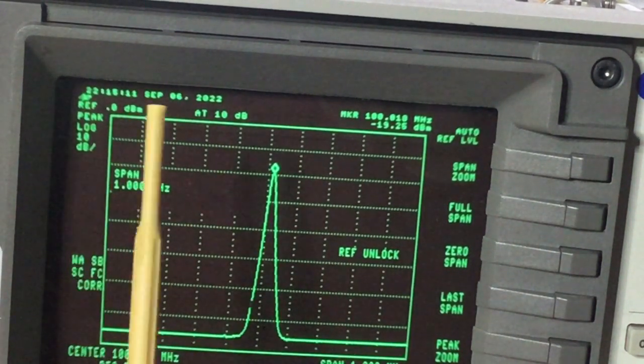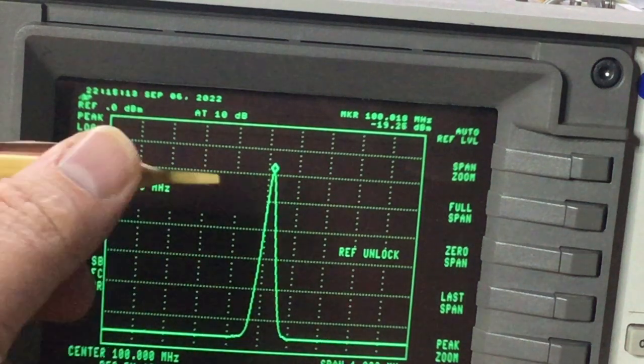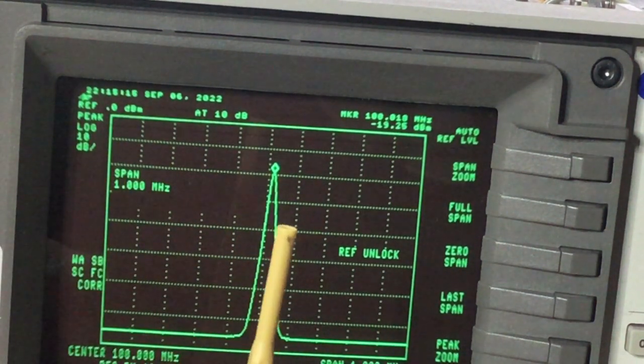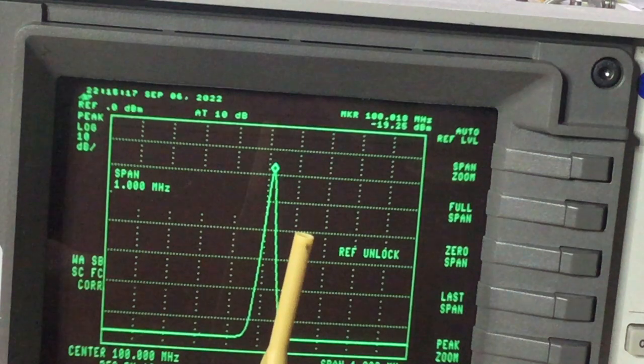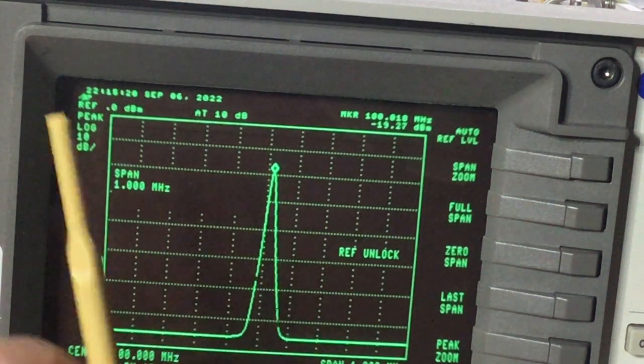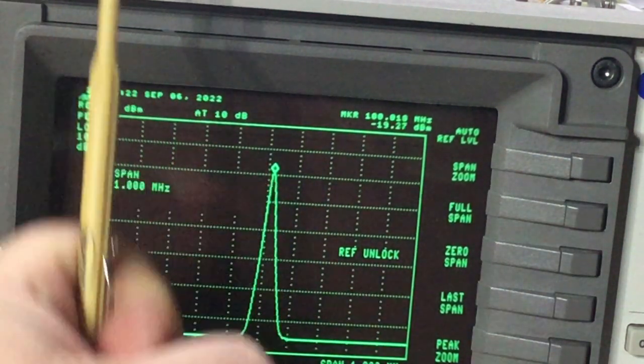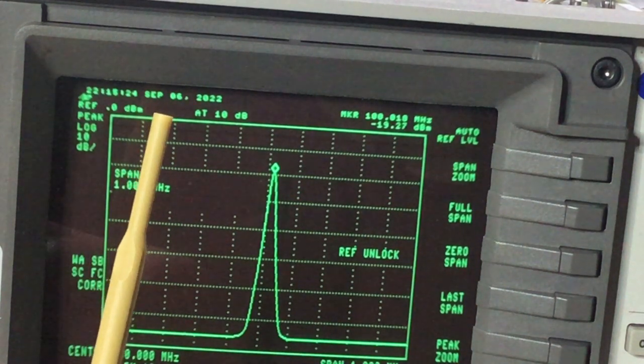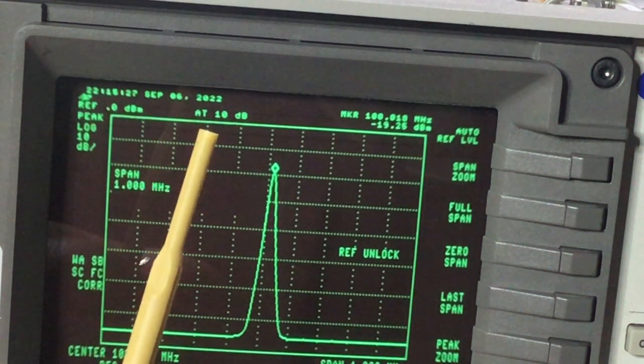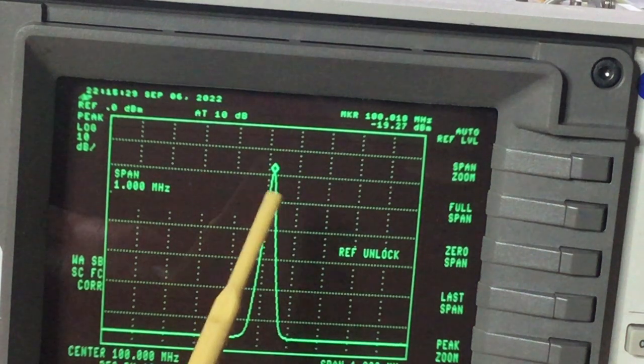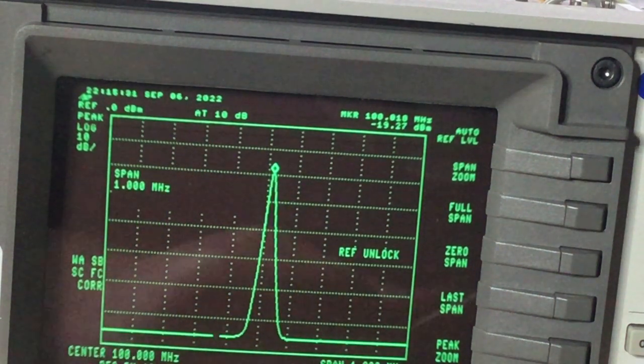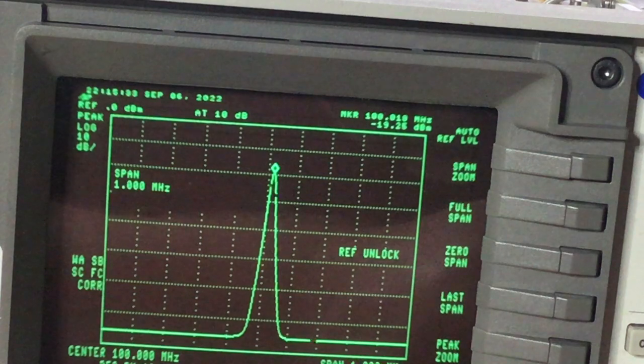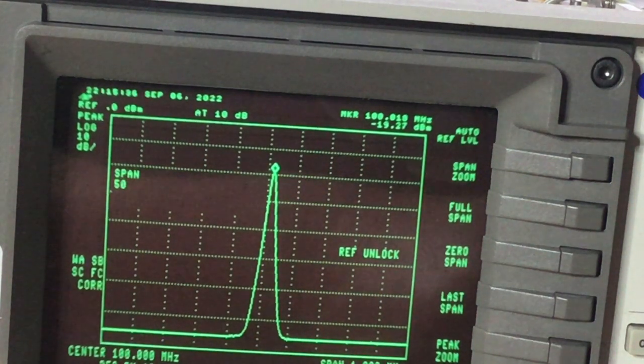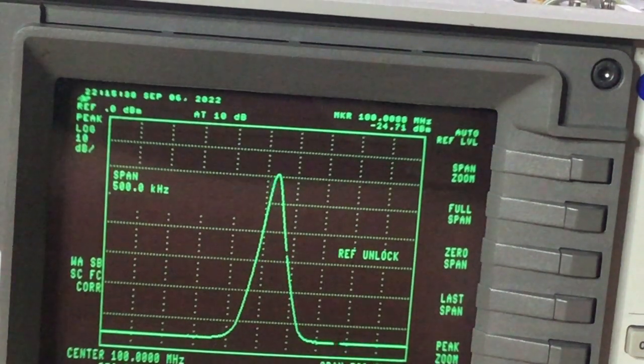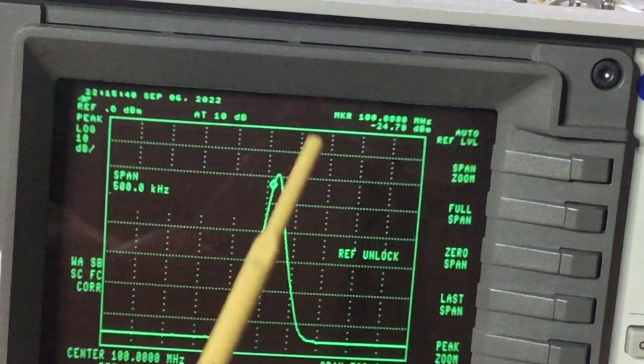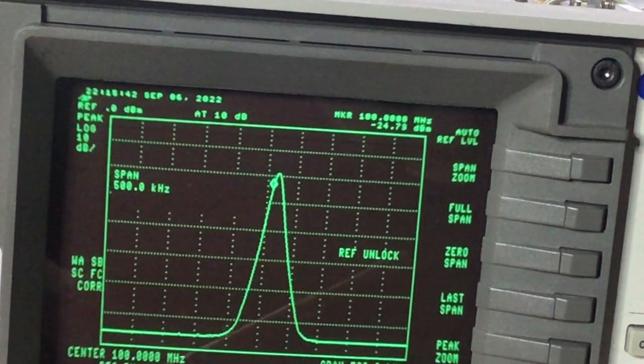So by netting the oscillator using the trimmer tool, we've fundamentally changed its frequency more closely to where the oscillator can grab it and then remain in the phase lock loop condition. And so now we're seeing this high stability. I mean, we would never have got that. With the span there, if I put that now at 500 kilohertz and look at that, we're still seeing that signal on the screen, and that certainly would not have been possible.